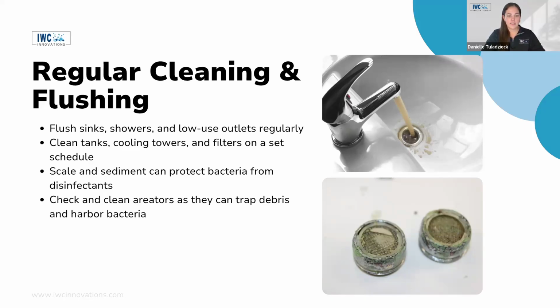Regular flushing of infrequently used sinks, showers, and other low-use outlets like emergency eye wash stations keeps fresh water with maximum disinfectant levels moving through the system and physically disrupts biofilms that might establish on the pipe's interior surfaces. Components of your system should all be cleaned on a schedule to reduce scale and sediment buildup, which can shield bacteria from disinfectants. Something that's often overlooked are faucet aerators. These small mesh screens can trap organic matter and sediment, creating a breeding ground for bacteria, including Legionella. If not cleaned or replaced regularly, aerators can reintroduce bacteria into the water system and increase exposure risk. You can also consider laminar flow attachments as a replacement to traditional aerators to reduce aerosol risks at the sinks.